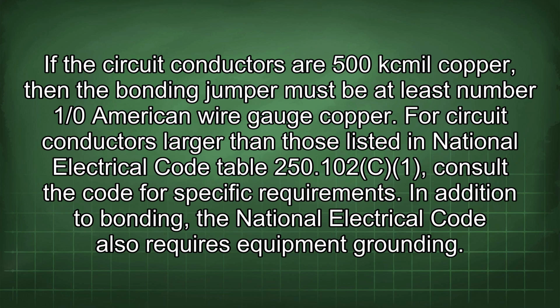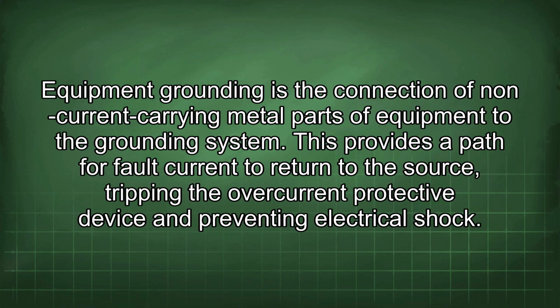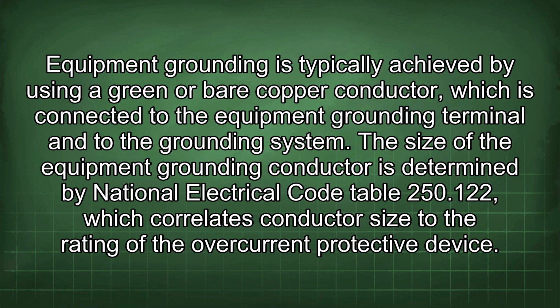In addition to bonding, the National Electrical Code also requires equipment grounding. Equipment grounding is the connection of non-current carrying metal parts of equipment to the grounding system. This provides a path for fault current to return to the source, tripping the overcurrent protective device and preventing electrical shock. Equipment grounding is typically achieved by using a green or bare copper conductor, which is connected to the equipment grounding terminal and to the grounding system.